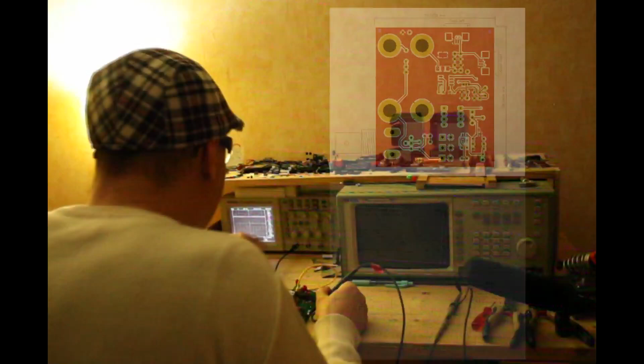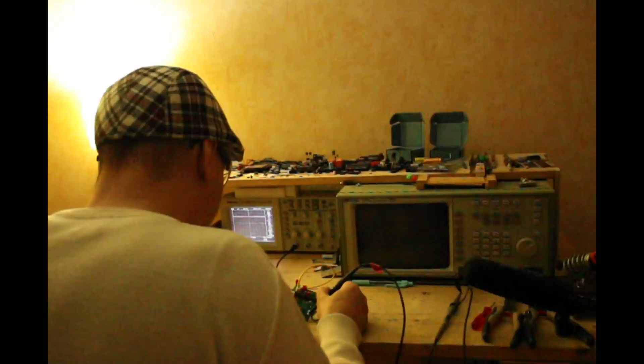The multimeter reading 9.99, 10.00, we are good. Tektronix reading, I can only get 10.1 average. I don't know if it's possible to get more digits, but I couldn't figure out, so 10.1. If we have some calibration method, we can use them through this TP3 with the jumper JP1 open. We want the TP3 to output our voltage ref.